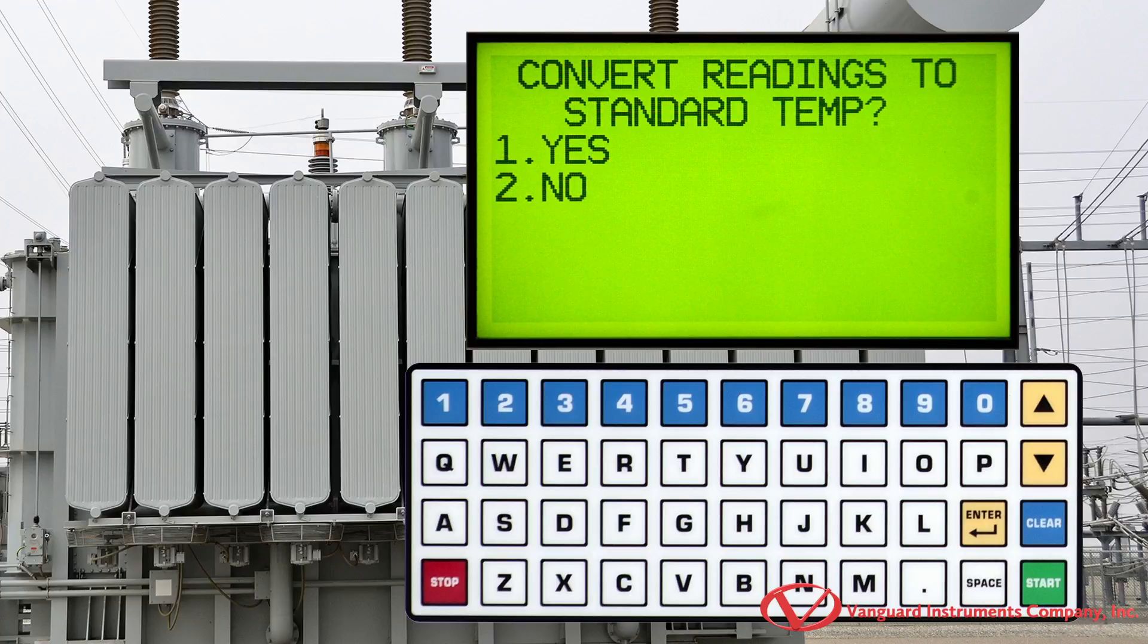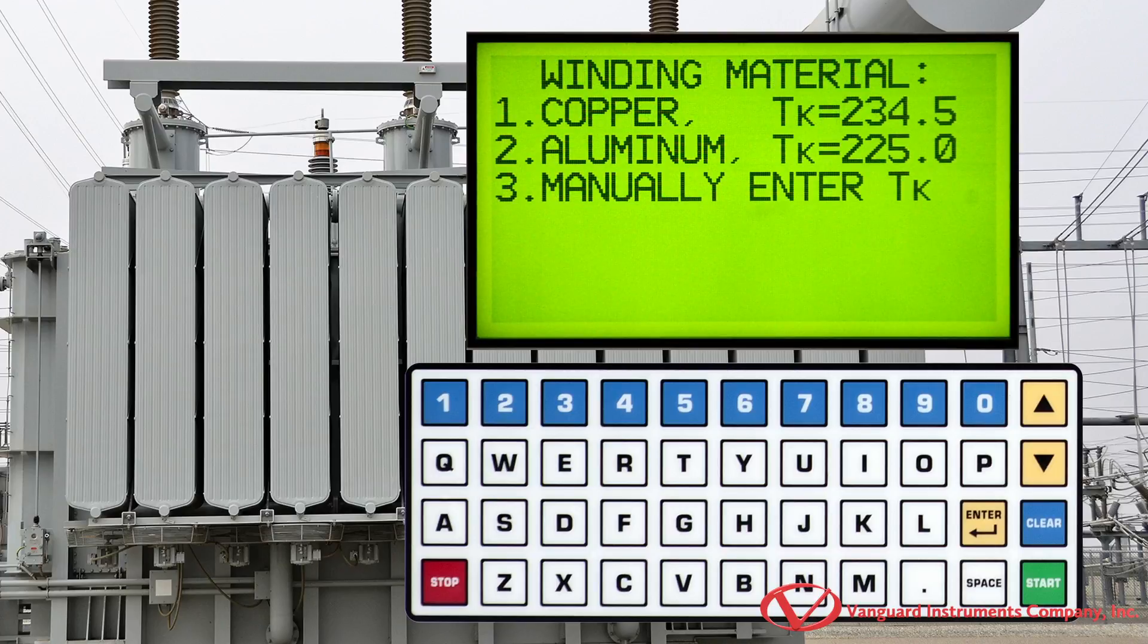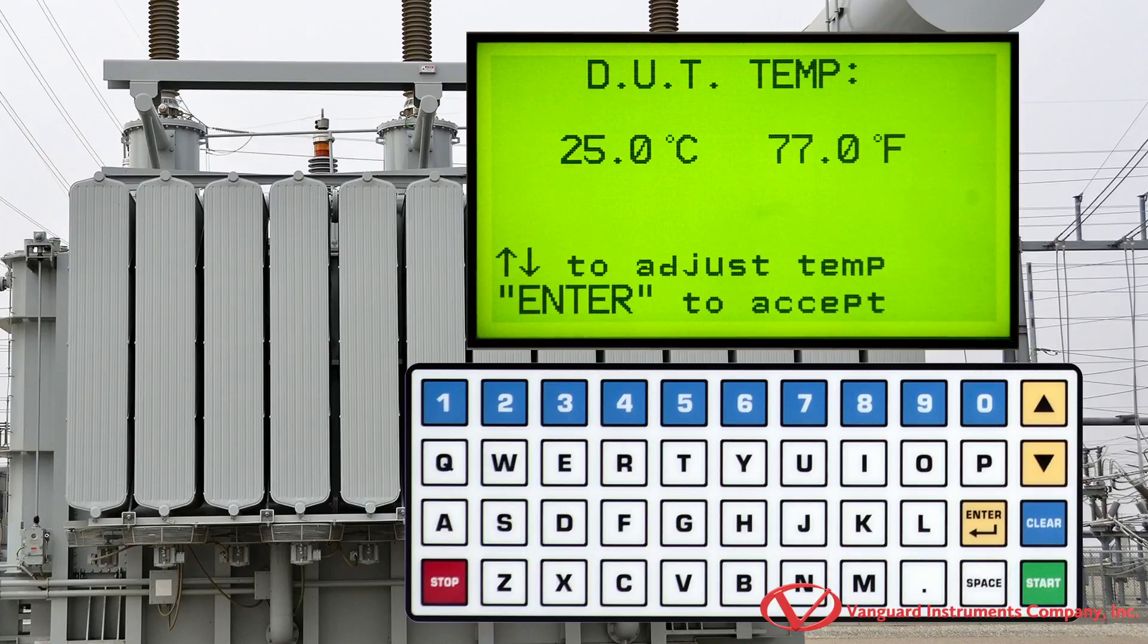We are now given the option to convert our readings to standard temperature. You can select this option if you know the winding material's temperature constant value. Let's press the 1 key to select yes. From this menu you can select the provided values for copper and aluminum windings, or manually enter the constant value by pressing the 3 key. We'll press the 1 key for copper since our transformer uses copper windings.